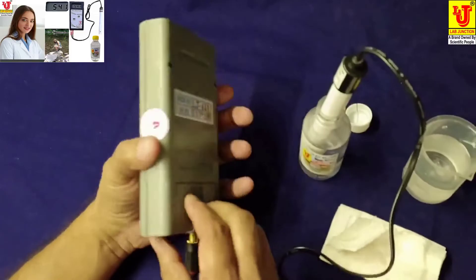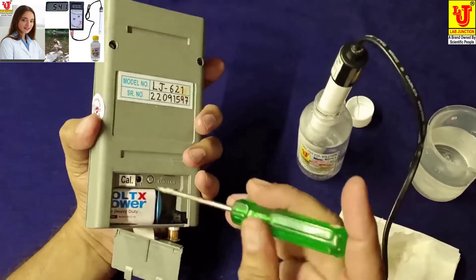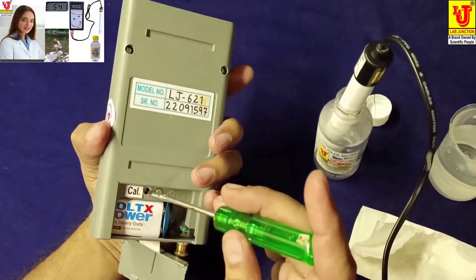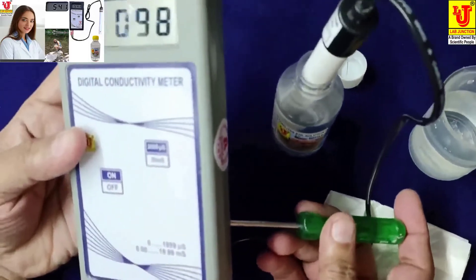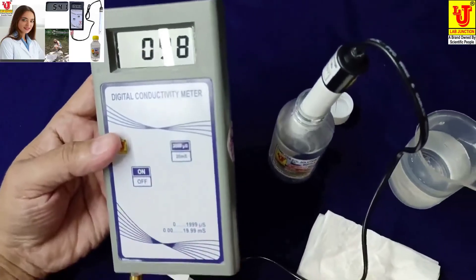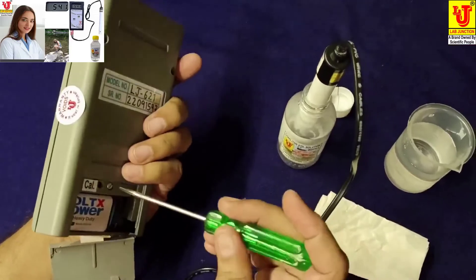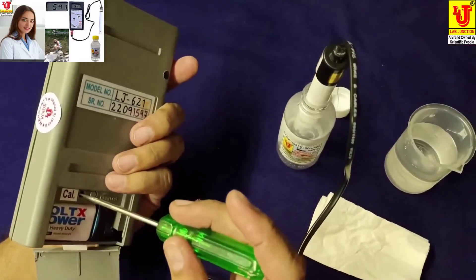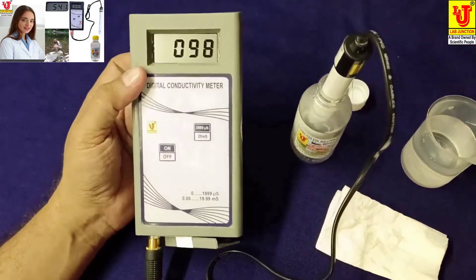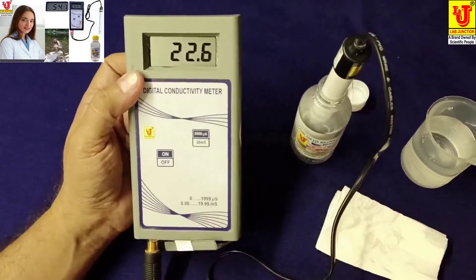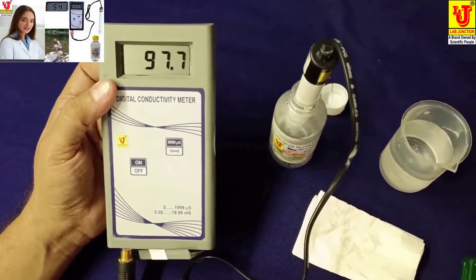If you again calibrate this, directly you can take your screwdriver, insert in this cal screw and move this and recalibrate this. Directly dip your conductivity cell in the conductivity solution and insert your screw on this cal screw and rotate to your desired value.